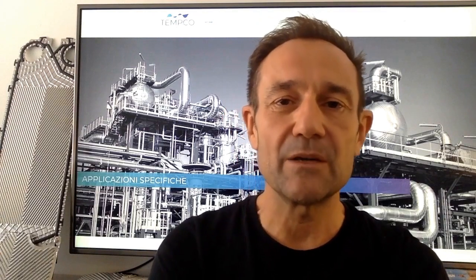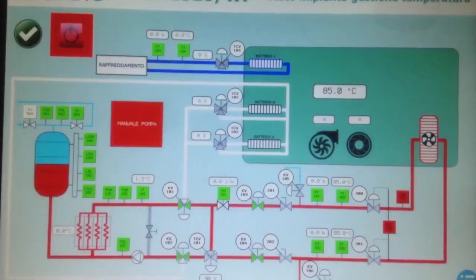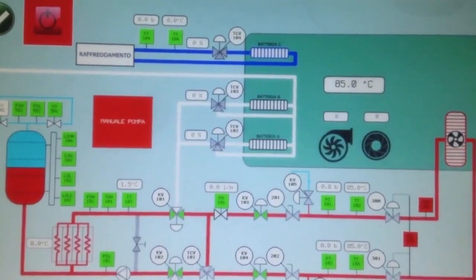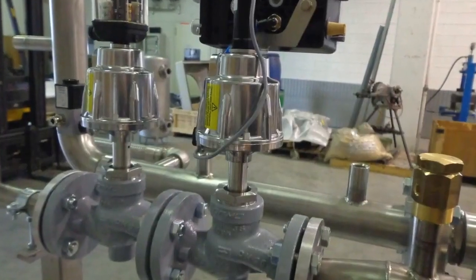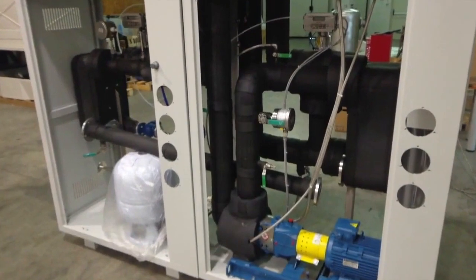This is because the risks of fluid contamination are high. Having glycol ending up inside a boiler or vice versa, condensation ending up inside a chiller that needs to operate with glycol are very risky elements from the point of view of temperature control. There is no comparison. We can act with modulating valves or with a system of bypass valves and regulation that allows us to have an extremely fine and refined level of temperature control with very high temperature change speeds. This is a solution now fully embraced.